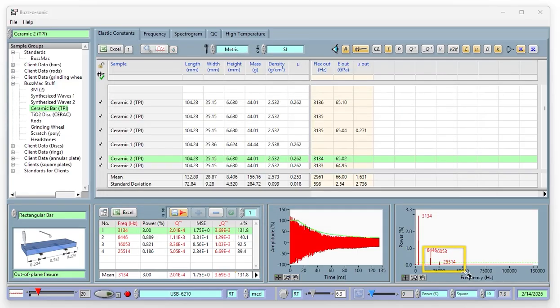These peaks here, those peaks are the overtones. This peak here is the fundamental flexural frequency. Now, one thing to notice, we measure this at 10 Hertz. That's the resolution. It means that the waveform is measured for a relatively short period of time.